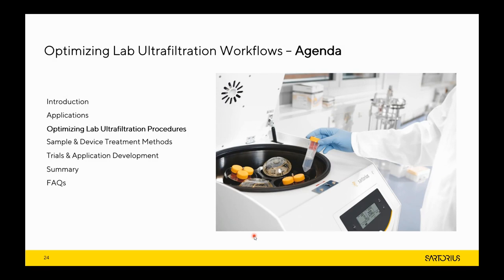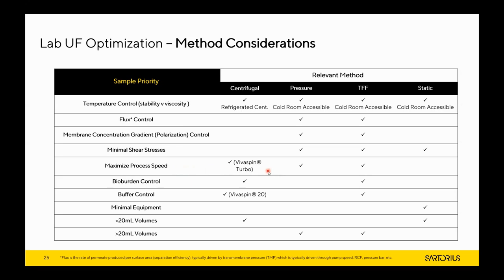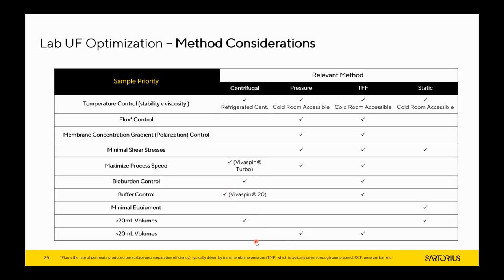Now, having painted a picture of the key applications, let's do a deeper dive into what to choose to optimize. When it comes to method selection — whether centrifugal, pressure, TFF, etc. — it really depends upon your sample priority. If temperature control is critical, use a refrigerated centrifuge device or place a TFF or static device in the cold room. If flux control is important, pressure and TFF work well. For maximum process speeds, look to the VivaSpin Turbo devices and TFF for larger volumes. If you need bio-burden control, centrifugal devices are preferred. There are too many specific points to cover all of them here, but the webinar recording is available to revisit these recommendations.